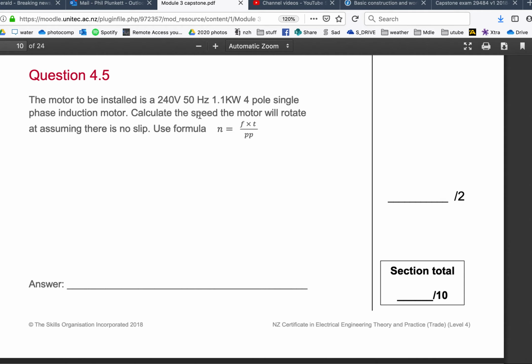Motor, calculate the speed. We did that just up there. Remember, it's F times 60 divided by the number of poles. F 50 times 60, 3000 divided by the number of pairs of poles, sorry. So 4 poles would be 2 pairs. So it's going to be 50 times 60 divided by 2. 50 times 60 is 3000 divided by 2, which will give you an answer of 1500.